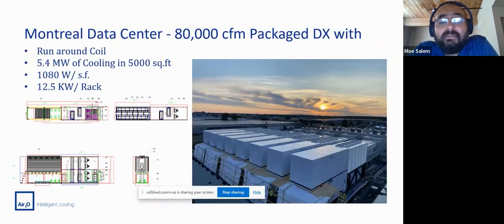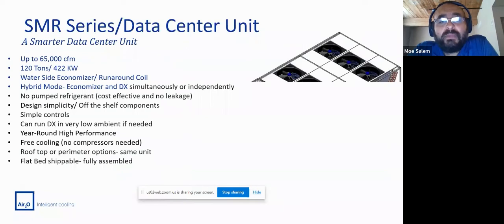This one here is a data center. It's up in Montreal. This is the largest data center per capita as far as how many servers per room. We have, I believe, 12 rack or 14 rack, each one at 400 kW, total at 5.4 megawatts. Yeah, 12.5 kW per rack for 400 racks, I believe. So we have about 5.4 megawatts of cooling in 5,000 square feet, which is the highest amount of megawatts per square foot per capita.